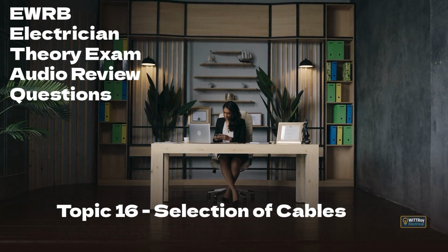Pause. 5, 4, 3, 2, 1, 0. Correct answer is option B. Tables assume specific conditions. If you skip derating, voltage drop, and loop impedance checks, the cable may overheat, equipment may undervolt, or protective devices may not trip fast enough.